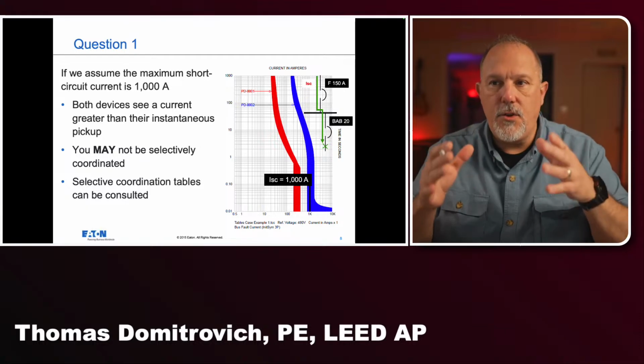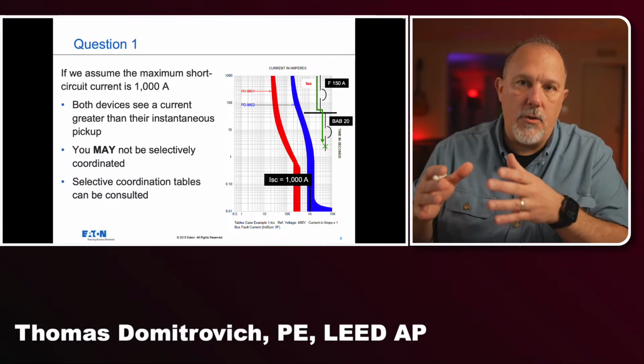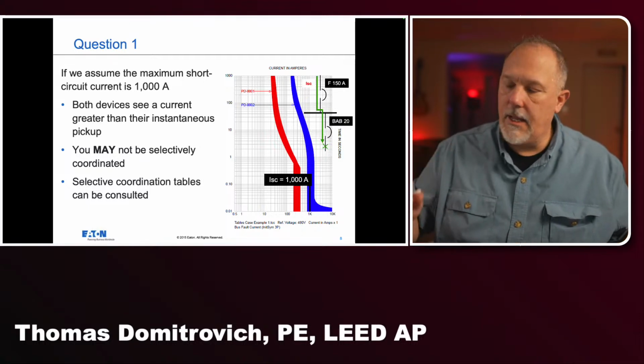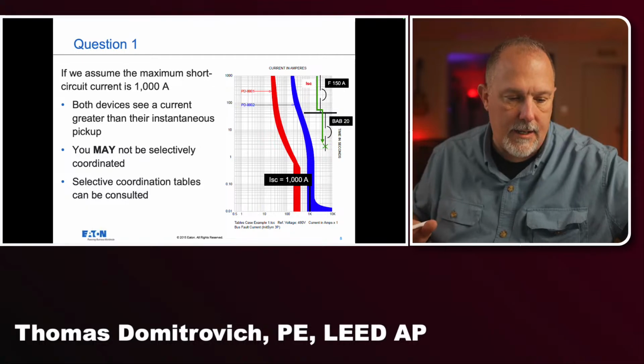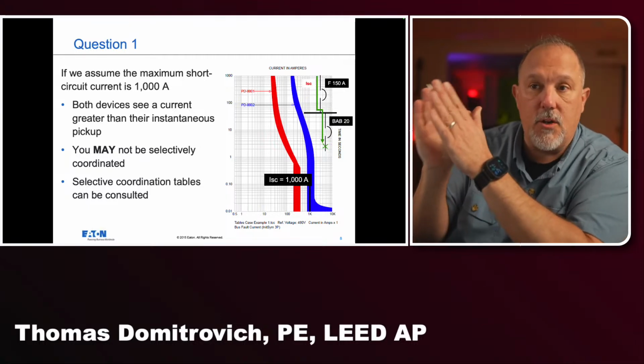So whenever you're looking at trip curves, anytime that you're looking at trip curves, you have to consider what the available fault current is for those trip curves. So if you're looking at time current characteristic curves, the engineer should be plotting on that time current curve what the available fault currents are at the various parts. In fact, just like in this image, I have the one-line diagram up at the top right-hand corner of the TCC curve.